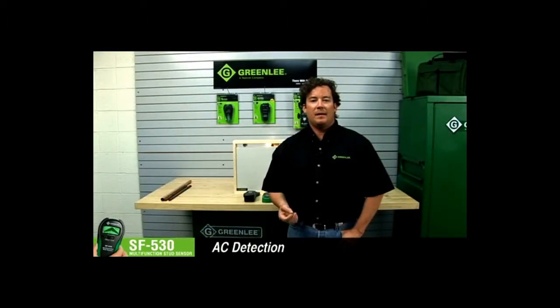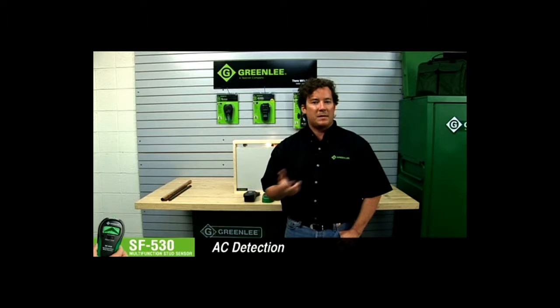Sensitivity to AC depends on how close to AC current the unit is when you turn it on. It looks for whatever AC current is present and then looks for more. So keep in mind that AC detection is not a super high precision locator of AC current. It's simply a warning that the unit senses the presence of AC, and the user should exercise caution and turn off circuit breakers, for example, before cutting into a wall with a saw.